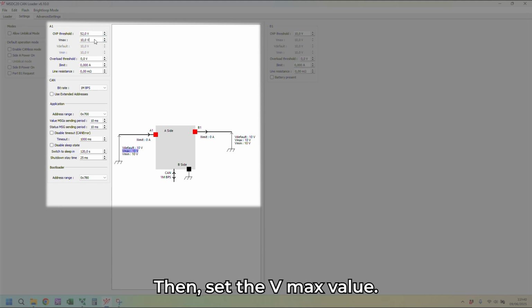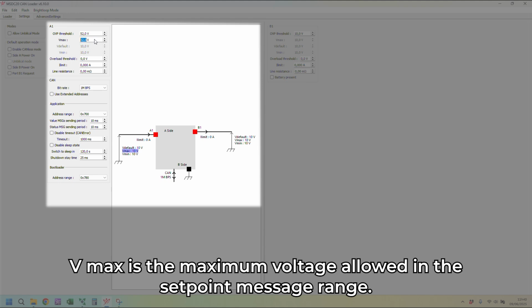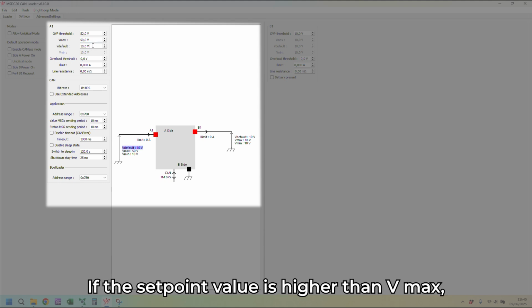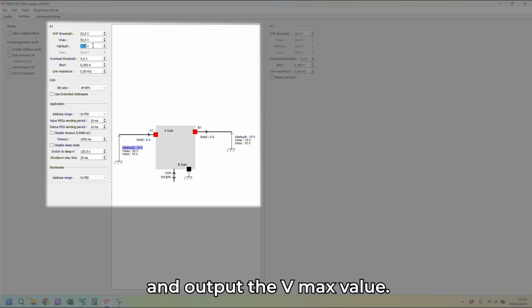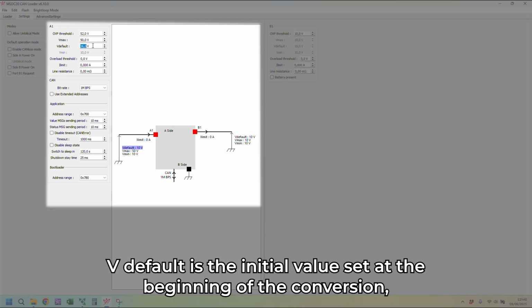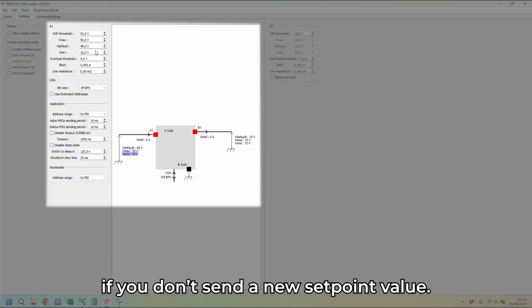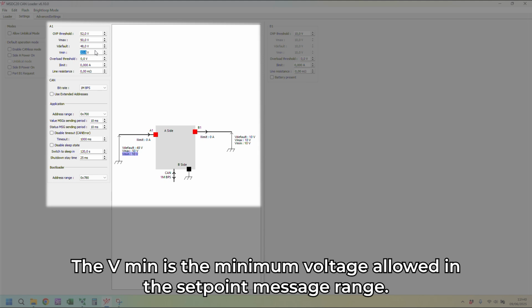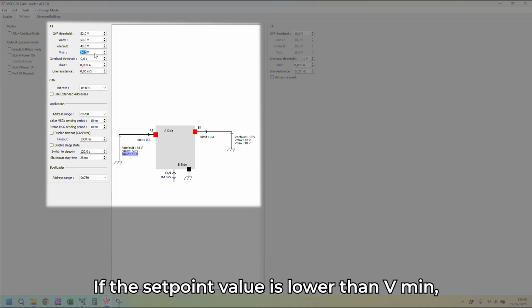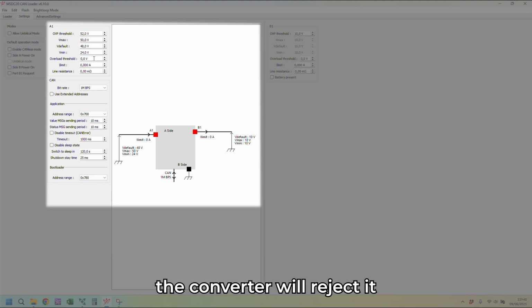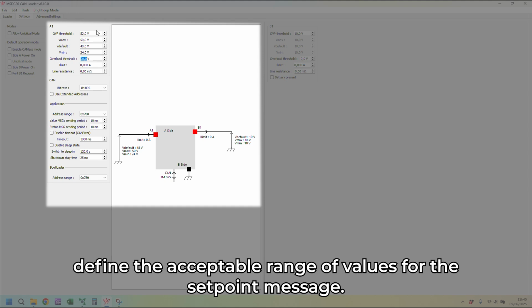Then, set the Vmax value. Vmax is the maximum voltage allowed in the setpoint message range. If the setpoint value is higher than Vmax, the converter will reject it and output the Vmax value. V-default is the initial value set at the beginning of the conversion if you don't send a new setpoint value. The Vmin is the minimum voltage allowed in the setpoint message range. If the setpoint value is lower than Vmin, the converter will reject it and output the Vmin value. So, Vmax and Vmin define the acceptable range of values for the setpoint message.